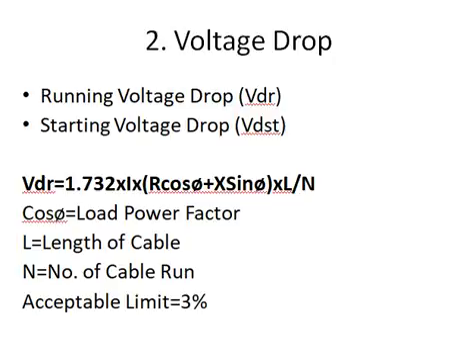The running voltage drop is calculated by this formula: VDr equals root 3, into continuous current rating, into (R·cosφ + X·sinφ), into cable length, divided by number of runs. Here cosφ is the load power factor. This value should be limited to three percent.